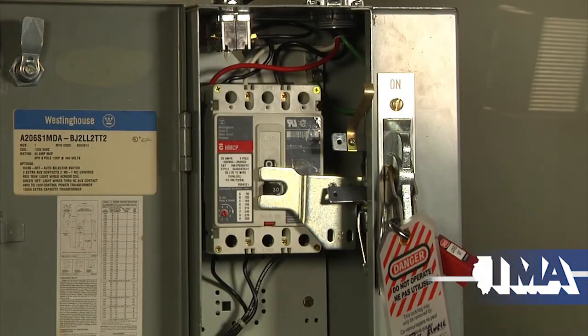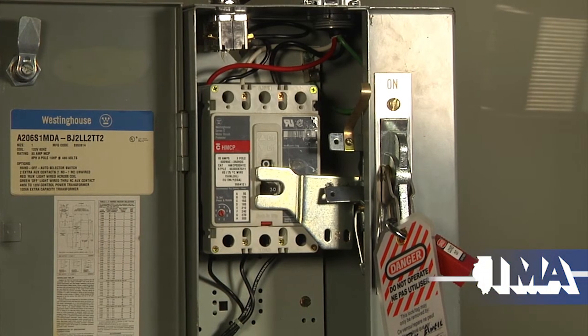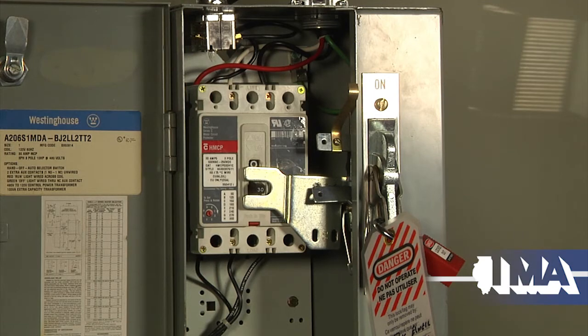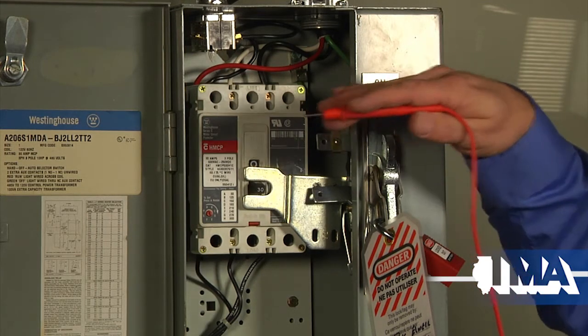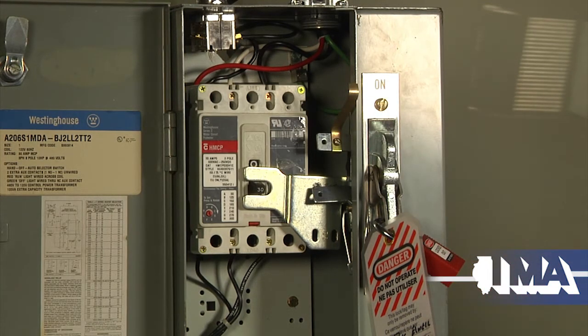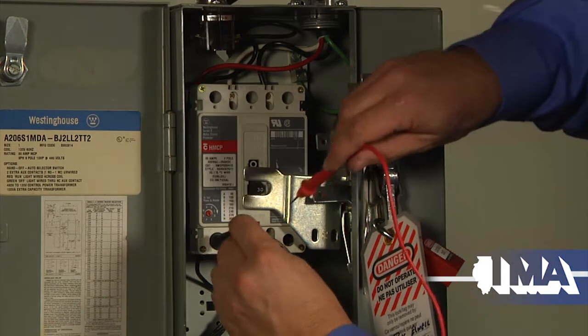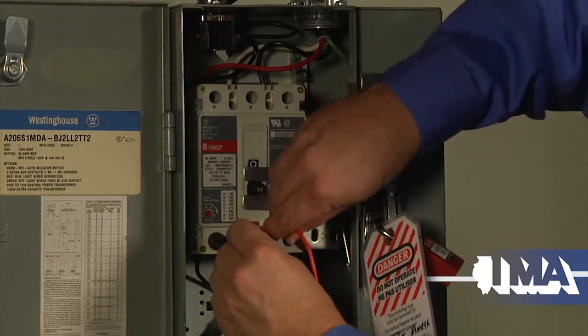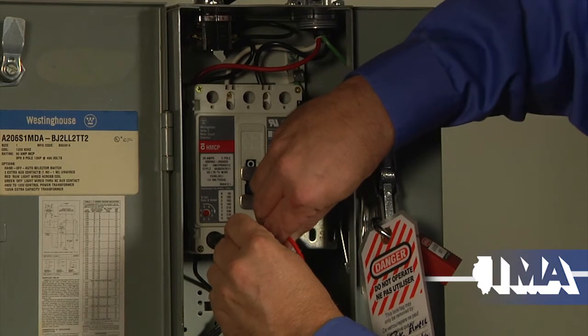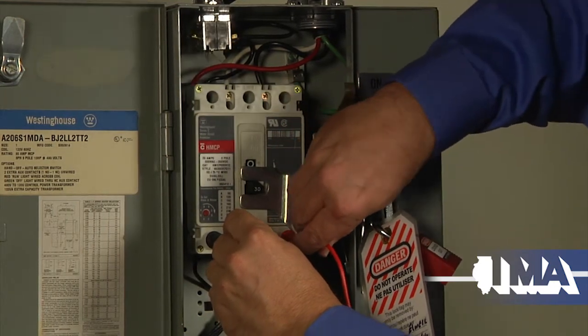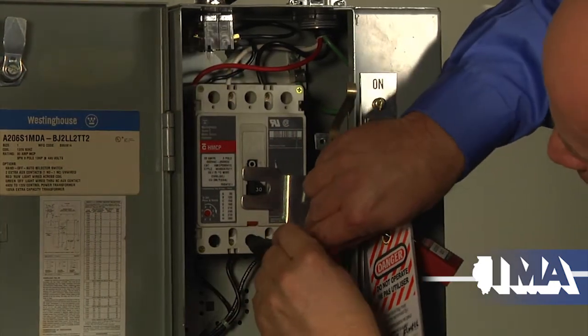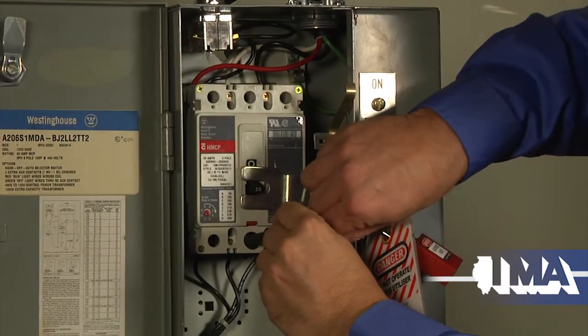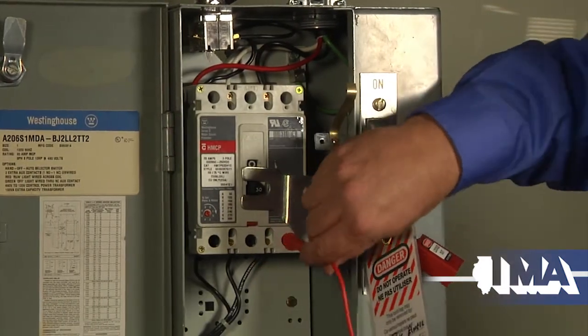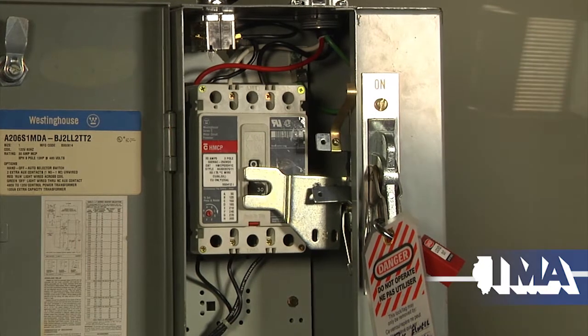Okay, so the next thing I'm going to demonstrate is what I term 6-point checks, which is phase to phase, phase to ground. That's going to verify that we have no primary power coming into this controller or this control unit. So I'm measuring phase A to B, or L1 to L2, L1 to L3, and then L2 to L3. Okay, that's phase to phase. The next check is to ground. So I want to check all 3 phases to ground.